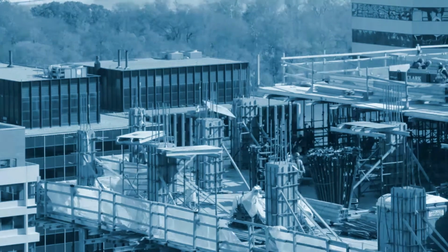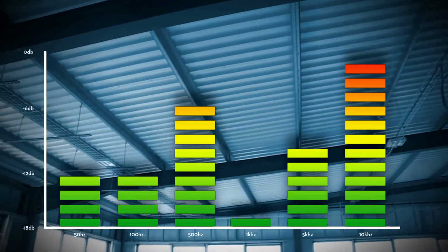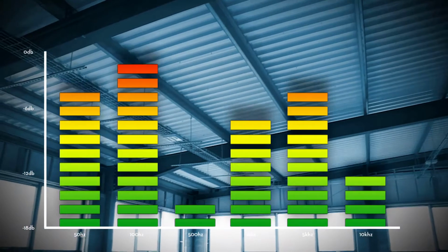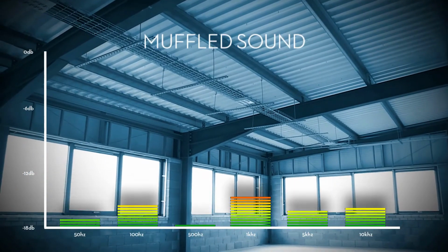Steelwork in buildings can seriously affect the function of any loop system. Metal presents an inductive load on the signal, which absorbs higher frequencies more than lower frequencies. For the hearing aid user, the result is muffled sound and a loss of intelligibility.